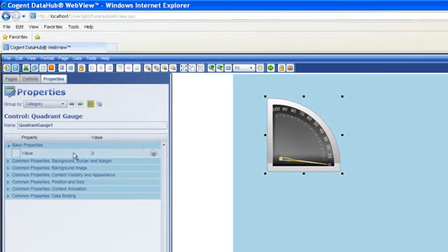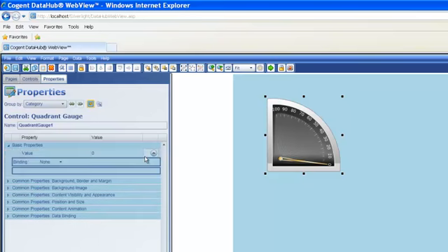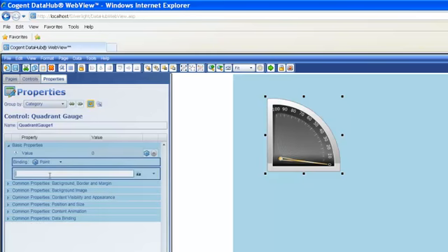I should now be able to click once and create an instance of that control, and sure enough, there's the XAML rendered, and you can see the one property that's been made available is value, in addition of course to the common properties, and I should be able to bind that. So if I now choose point and I enter PV and specify PV, you can see immediately my gauge is now reflecting the value associated with the process variable. So that's all working really nicely.